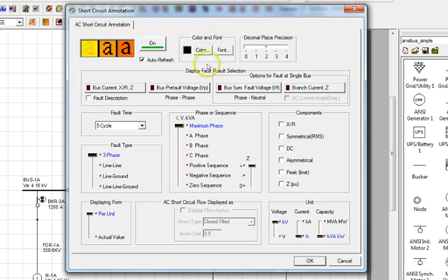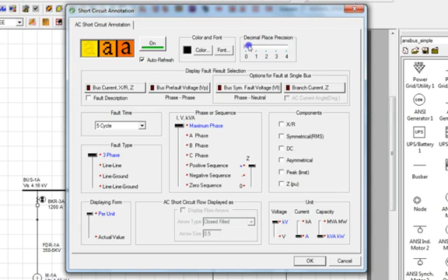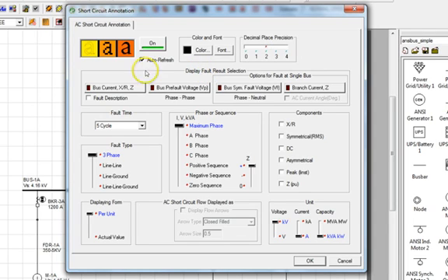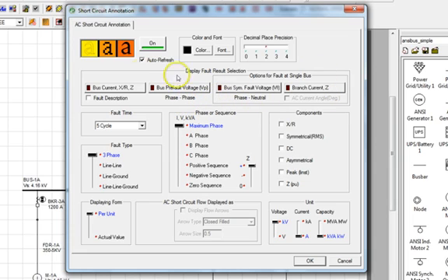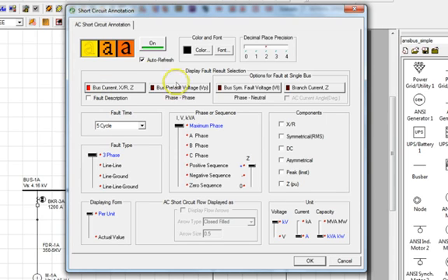In the Color and Font section, we can select the type of font we wish to use. The decimal precision with which to annotate the results can be defined by moving the slider to the desired value. In the Display Fault Results selection, we can choose which results and parameters will be displayed on the single line diagram. Let's select the button that enables bus current, X over R ratio, and impedance. We will not include the bus pre-fault voltage since we already know that this was preset to nominal in previous screens.